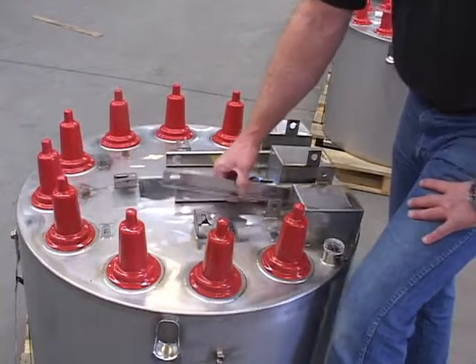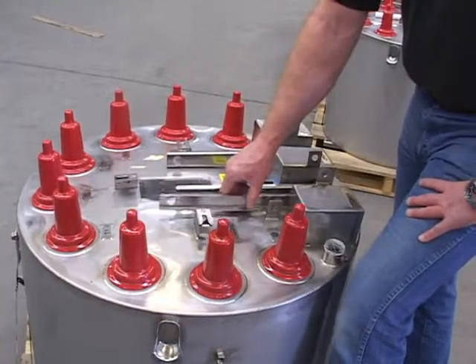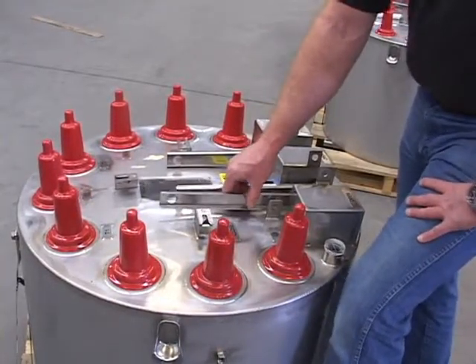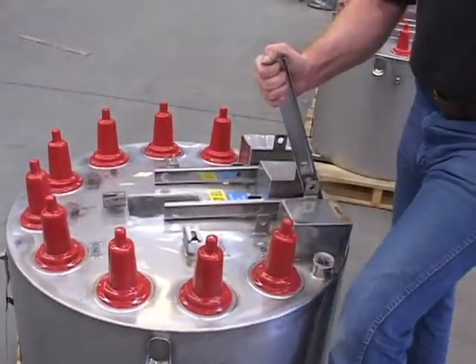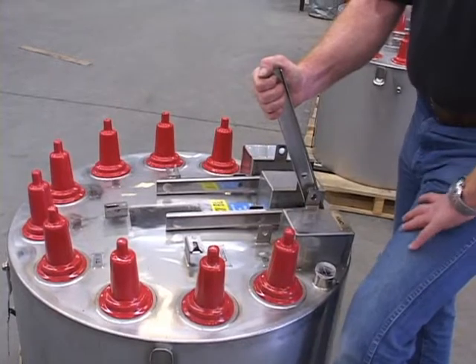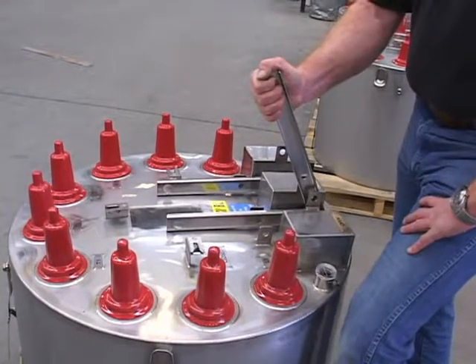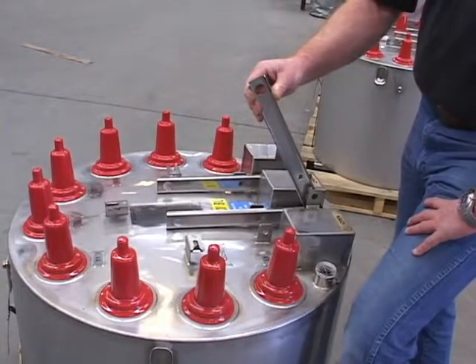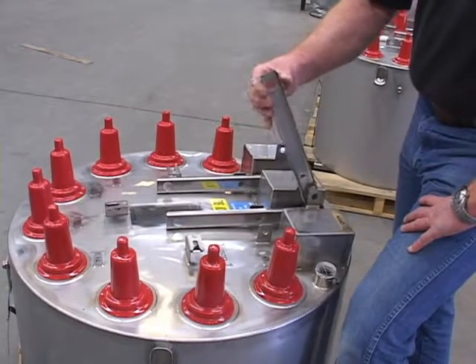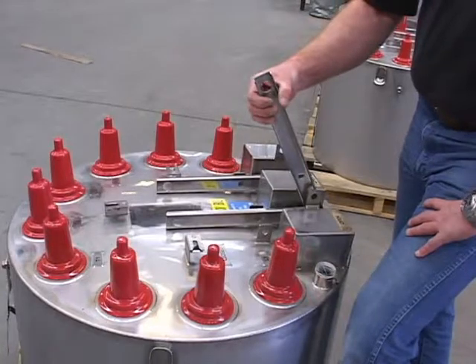The Trayer load break switch mechanism is a very simple but very powerful device. It requires substantial force to operate the switch mechanism. The heavy die spring driven toggle requires that the linkage be slotted so that the toggle can fly over top dead center and not be felt in the operating handle.